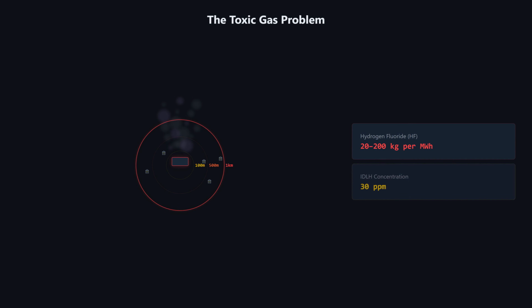Every megawatt hour of lithium ion battery can produce 20 to 200 kilograms of hydrogen fluoride when it fails. A typical grid scale BESS installation might hold hundreds of megawatt hours. That's potentially tons of HF released into the atmosphere. Add hydrogen cyanide, carbon monoxide, and phosphorus compounds. These gases don't just threaten firefighters, they threaten entire neighborhoods. Toxic plume modeling now shows evacuation zones can extend over a kilometer from a BESS fire. This is why separation distances matter enormously.